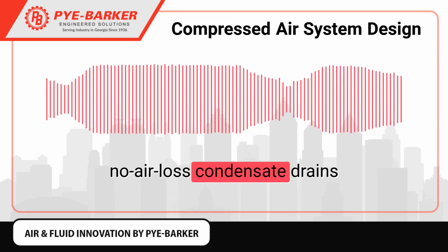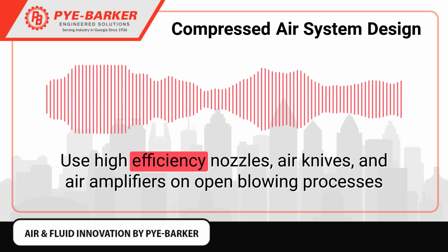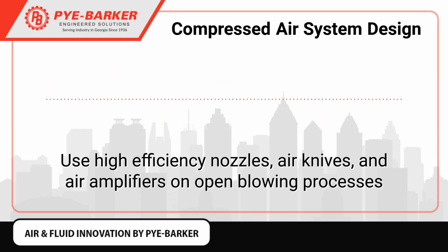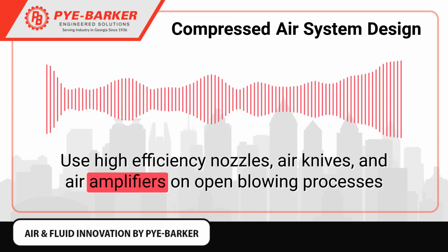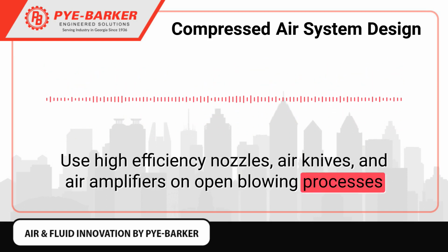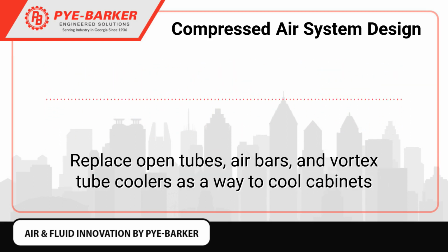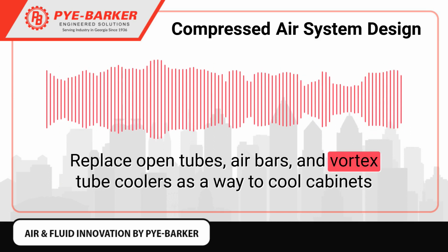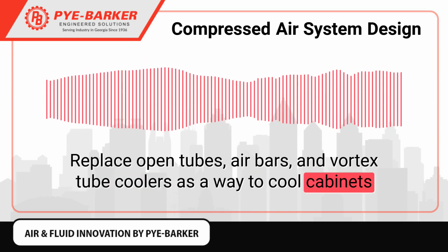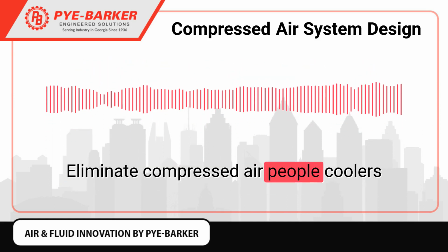install no air loss condensate drains, use high-efficiency nozzles, air knives, and air amplifiers on open blowing processes, replace open tubes with air bars, and use vortex tube coolers as a way to cool cabinets. Eliminate compressed air personal coolers.